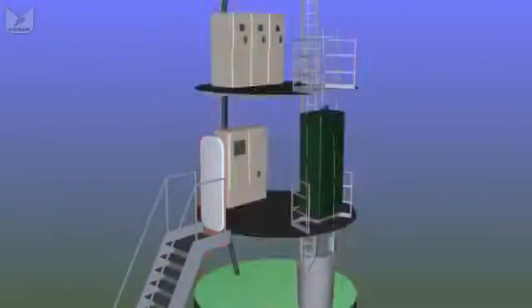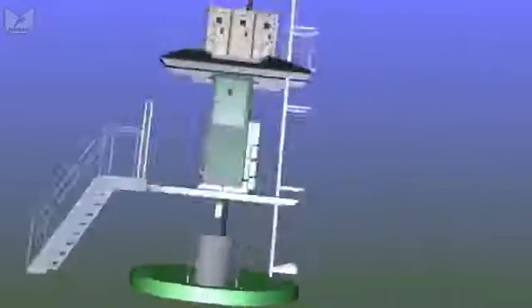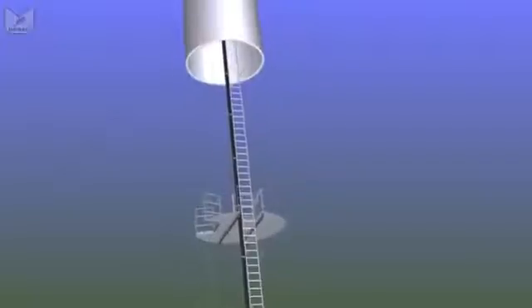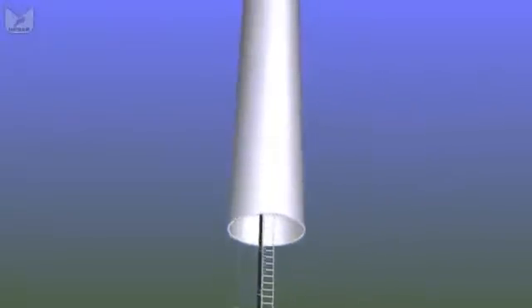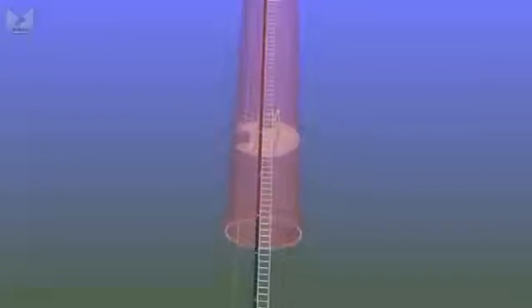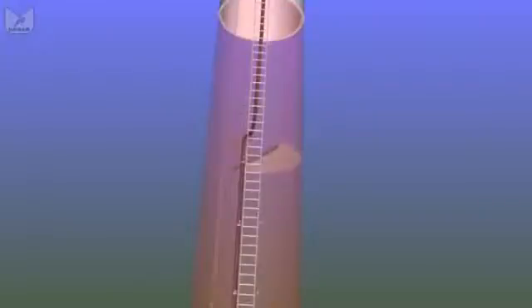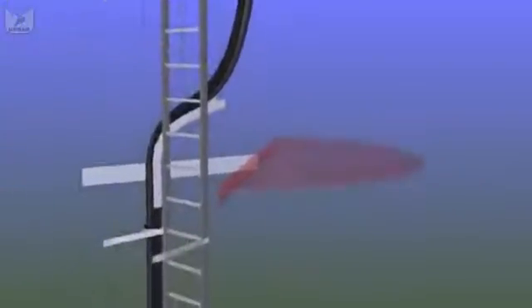That lift will take two people to the top of the tower, or nearly to the top, without them having to climb the single very long ladder. Almost all large turbines will just have a single run of ladder for the majority of the run up the tower. It will have a wire or rail system fall arrest device fitted to it, but it is still a long slog up the ladder, which is one of the reasons why service lifts are so important. Again the towers come in sections. Sometimes if we're running a long distance we haven't got room for a proper platform, we can put a half moon in place. No fall protection on the platform, but we assume you would keep your lanyards connected.